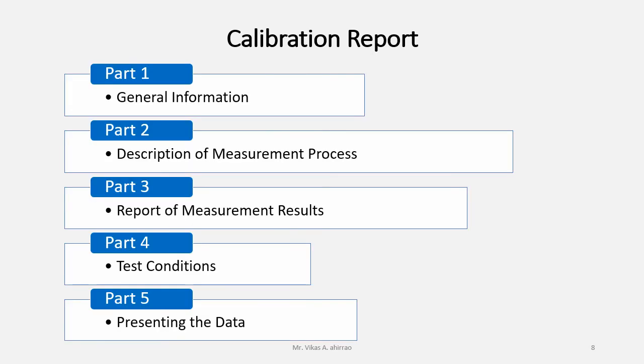A calibration report. As the name suggests, it is a detailed document. It is not compulsory for a calibration laboratory to issue a report or certificate, but depending upon the requirement from the customer or the user, the calibration laboratory may issue a calibration report or a calibration certificate. The calibration report consists of mainly 5 different parts.